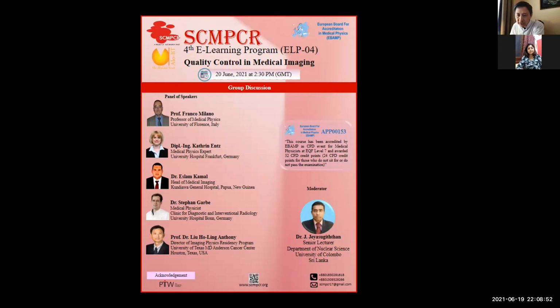By viewing MR image, how can we assure that image quality and resolution are optimal? So you are talking about optimization. I assume it's not the QC testing. QC testing has certain criteria. If we image at 1 millimeter, we want to make sure it has 1 millimeter resolution. But you are talking about optimization. That really depends on clinical applications.